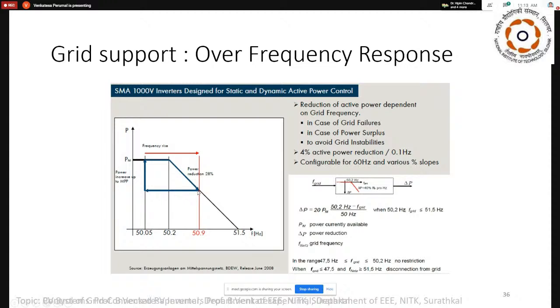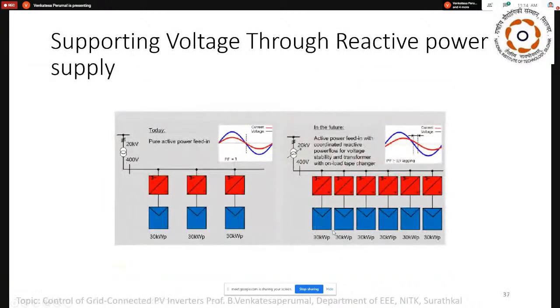But if the power demand is increasing, then the frequency will come down. Up to this point, it is not going to increase the power it has reduced. It will be maintained constant. At one point, at 50.05, it goes back again to the normal power condition. Basically, a kind of hysteresis loop is implemented over here to address the system stability.